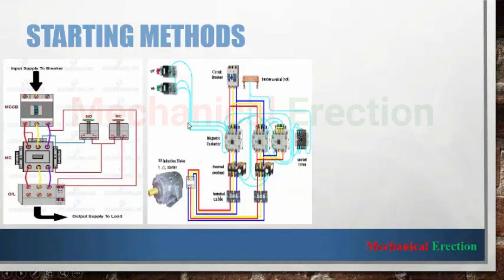Then star-delta starting. It is done to start a large motor where the starting current is too high. In such situations the motor is started in star connection and then switched to delta connection for full load running operation. First the motor is started through the star contactor, then switched after a certain period through a timer to the delta connection, and the motor finally runs in delta connection for its long operating period.